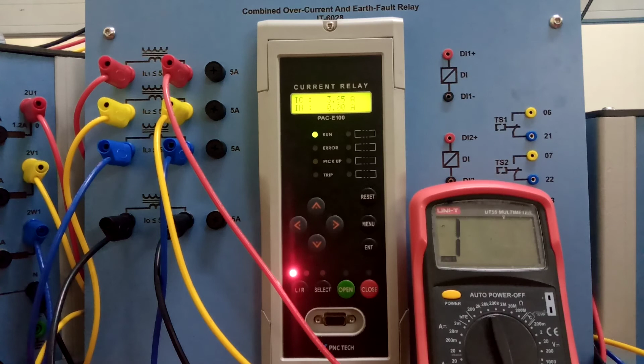Next, we have to connect this summation current transformer to the inductive load to simulate a fault on the sending end. The resistive load was for the receiving end overcurrent fault, and now there is an earth fault. If there is an earth fault on the sending end, we will be monitoring this fault, so again we have to connect this here.